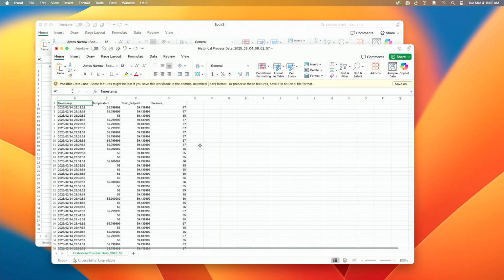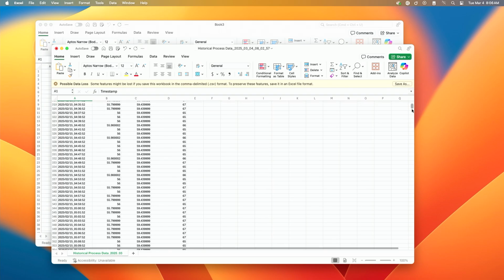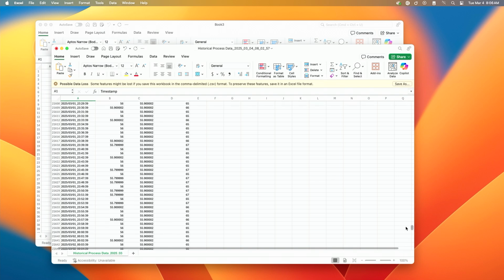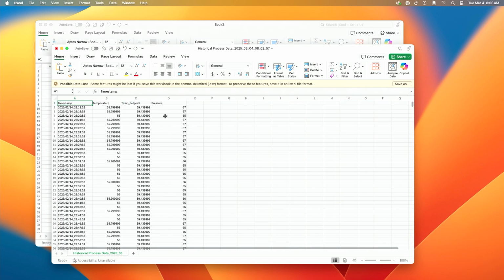And there we are. Okay, so you can see here's the data going all the way back to the middle of February. Okay, that's as far back as we could go and stay within our limit of 25,000 cells. Now, if I want to have more than that, so in this case, I wasn't able to go all the way back to the previous 30 days. I was only able to go back to the previous, let's say 15 or 20 days based on the number of entries. I could raise the number of entries in my setting for that particular time series chart above 25,000 to get all the data there. I could also do some aggregating of the data.